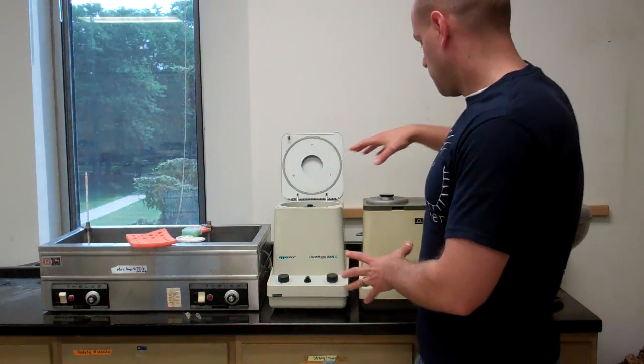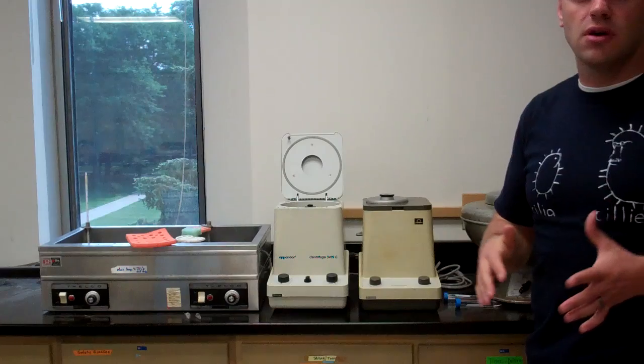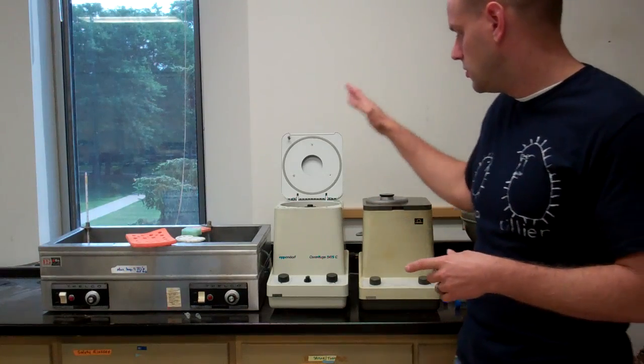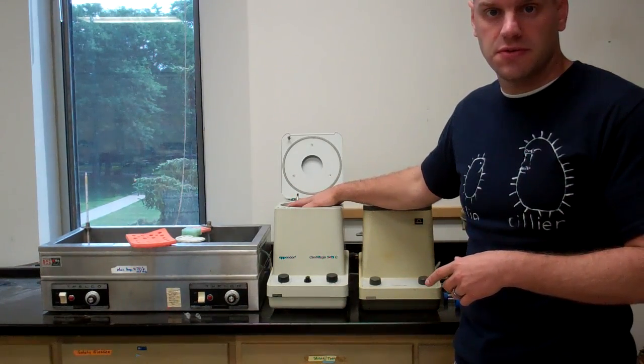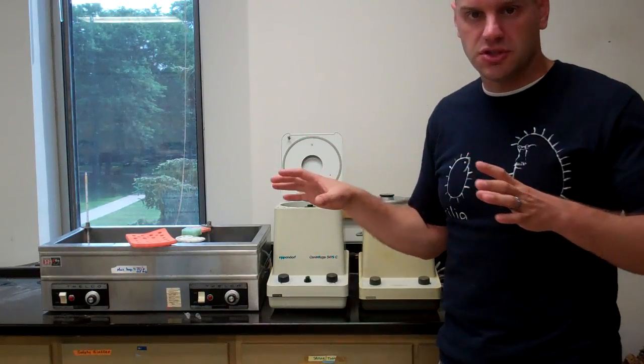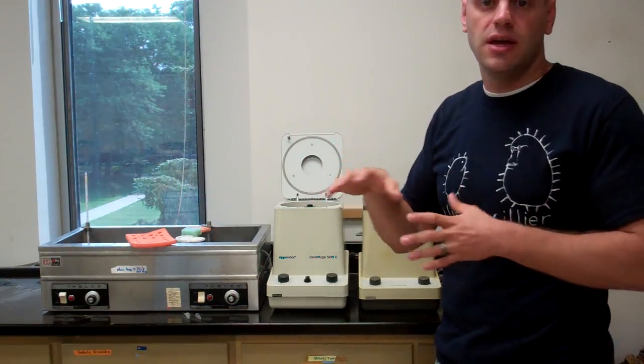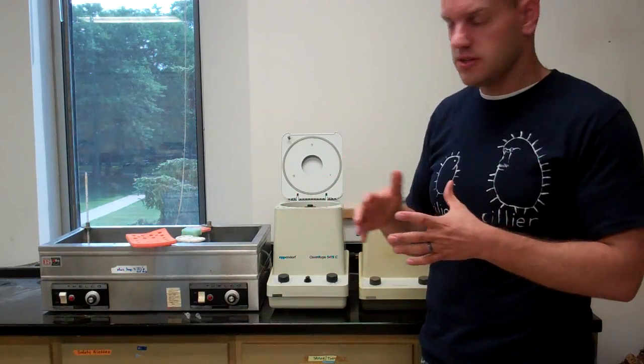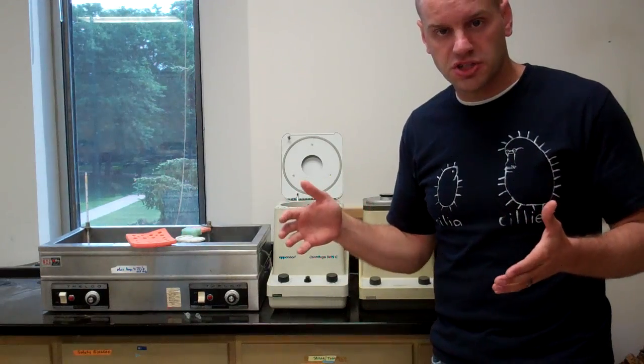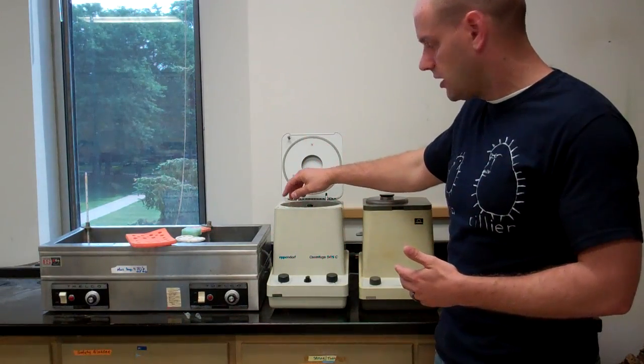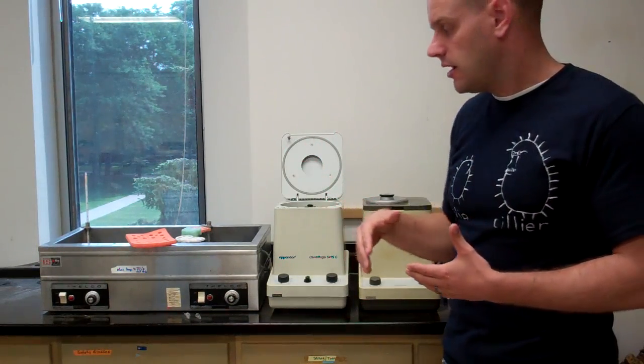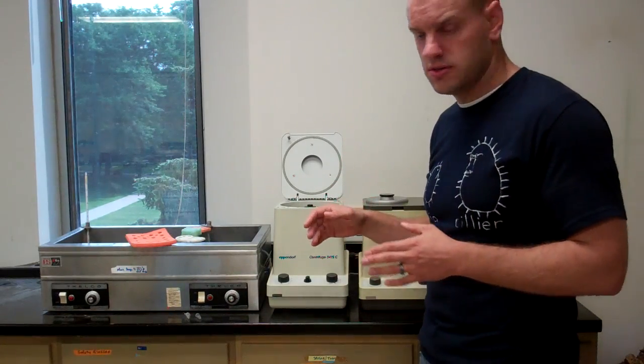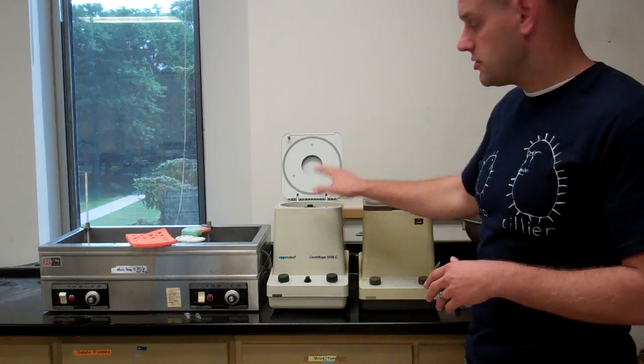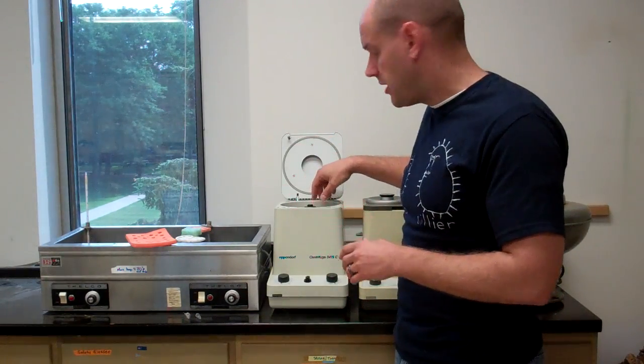When you're loading any of these centrifuges, you want to be sure that you're always balancing them. By balancing, I mean that you're never going to add just a single tube to one holder in the rotor. You want to have an equal distribution of weight across the rotor because, as I mentioned, it's going to spin these samples very quickly. Kind of like an unbalanced load in a washing machine, an unbalanced centrifuge rotor is going to start spinning and then be thrown off kilter with some fairly catastrophic results. So you don't want to ever spin an unbalanced centrifuge. Always add tubes such that the rotor is balanced.